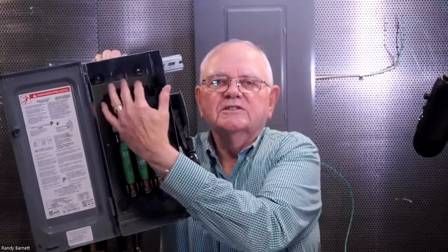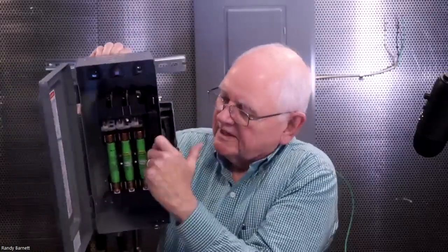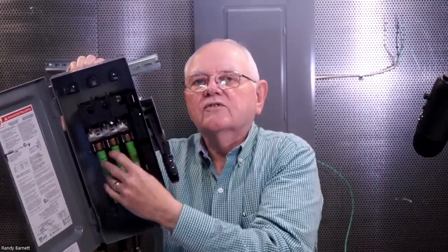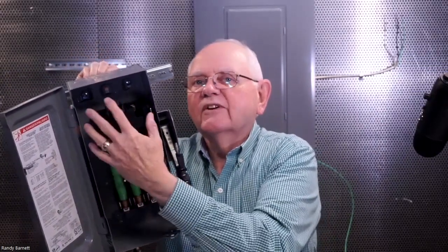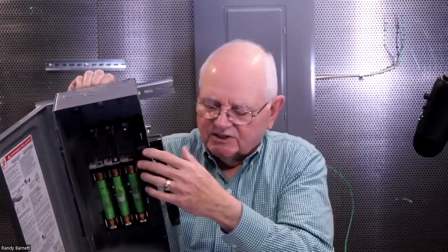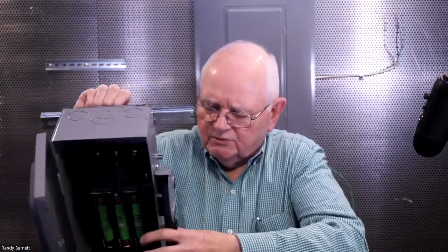And we know that if we open it up on the inside, we're going to see some knife blades up here and some stabs, which we can operate with the handle over here. And then we've got 3 cartridge type fuses. So there are some requirements for this safety switch, but let's talk a little bit about it. First of all, let's see if we can find a definition. Since we don't find a definition for disconnect switch in Article 100 of the NEC, let's see if we can find maybe a definition for safety switch. We don't. There's no definition for safety switch in the National Electrical Code.